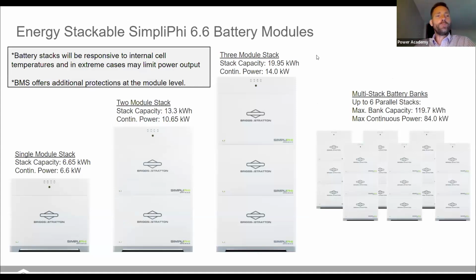lifetime standpoint. The 6.6 batteries, they're stackable batteries, so there are no wires, except for that final run from the controller at the top. So the battery itself consists of a base unit, modules that are 6.65 kilowatt hours each, and then a controller at the top. Out of a single stack module, you can get 6.6 kilowatts of power. So that's a very high power output rating. That's a C/1 rating. Typical batteries are C/2 or C/3, which means the fastest you can discharge them is 2 or 3 hours. This battery, you could discharge it in as little as 1 hour.